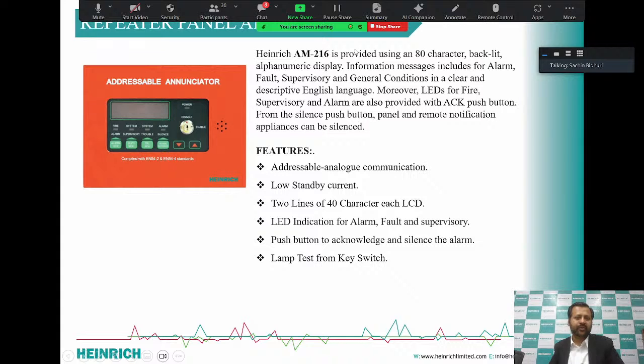This is the repeater panel. It is basically a dummy panel for the main fire alarm panel. Many a time the control room is a bit far from the towers, in case of societies. So we can have a repeater panel in each tower, and if any tower gets a fire indication or anything, a person can use it and provide signals to the main controller or to the people living in the society, I mean the tower, that there has been a fire breakout.